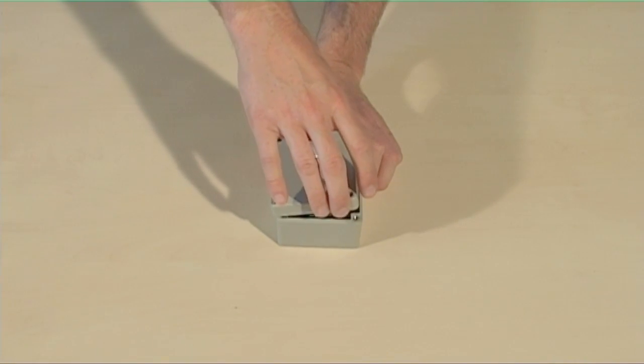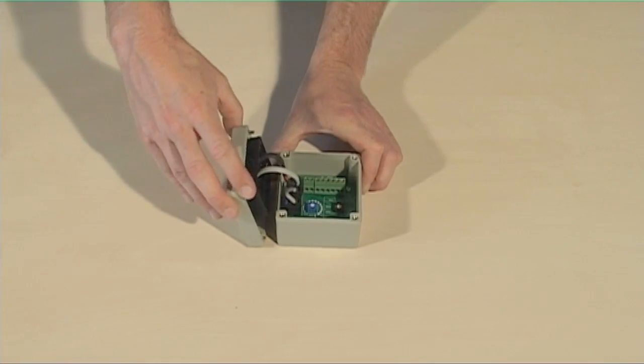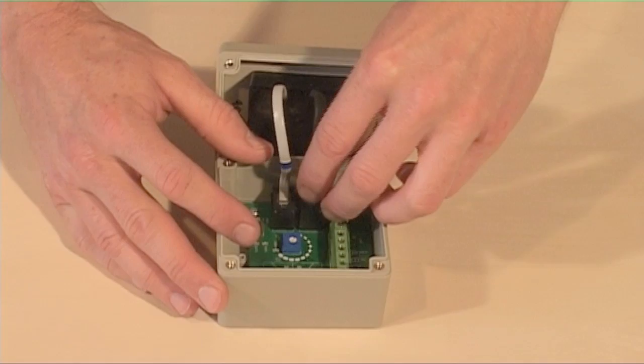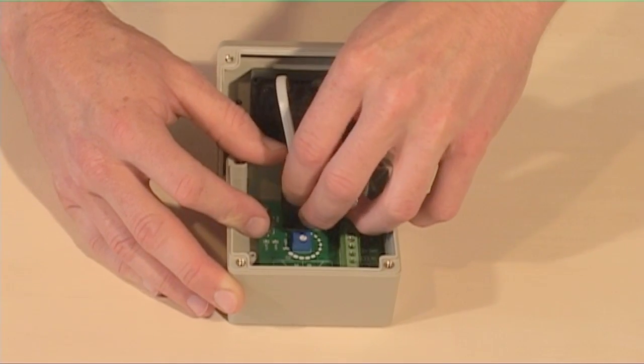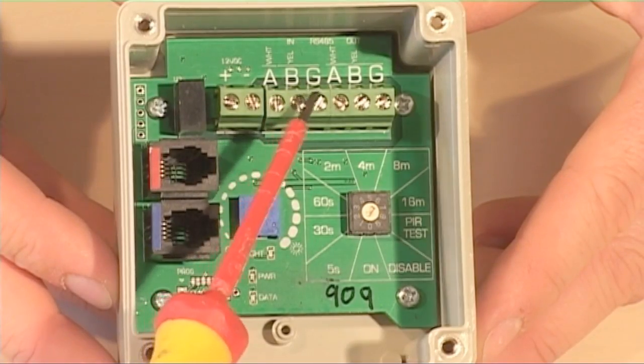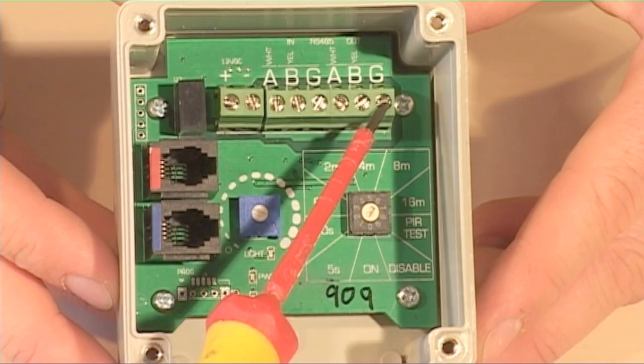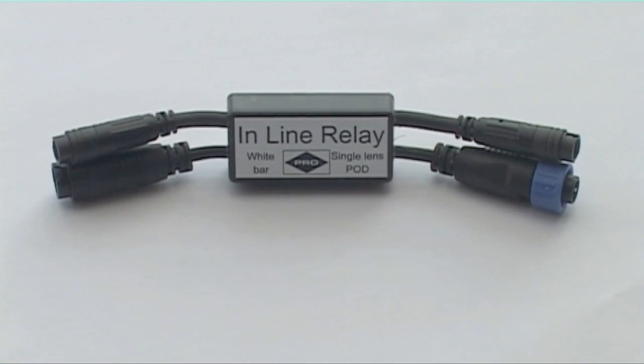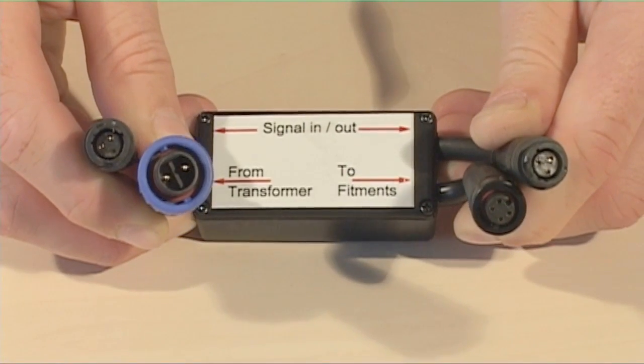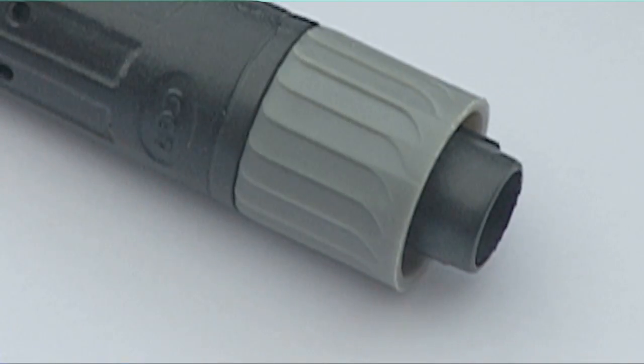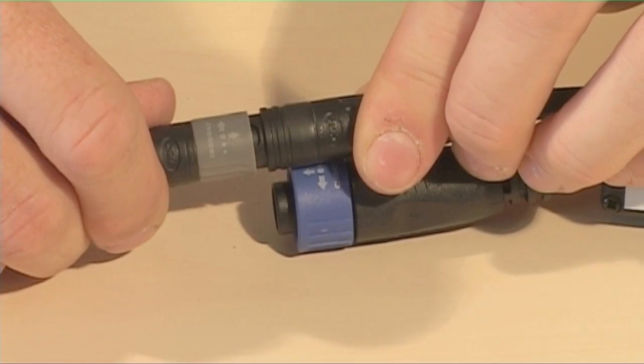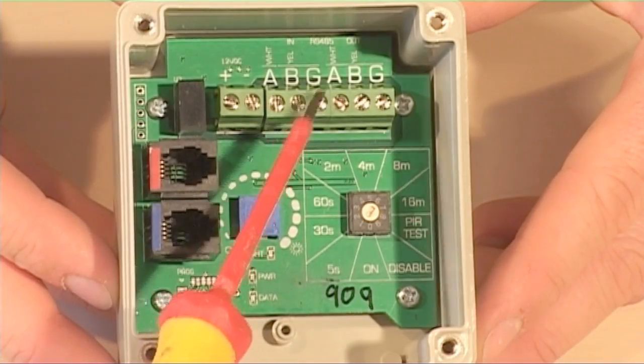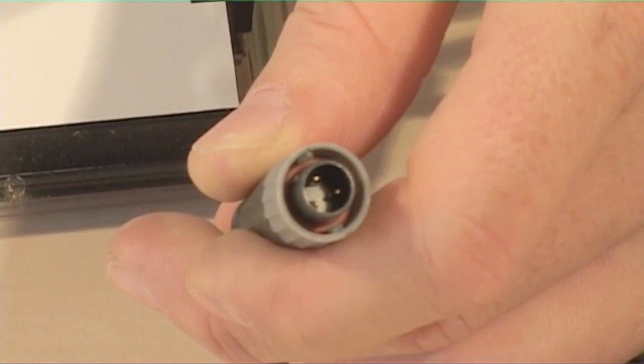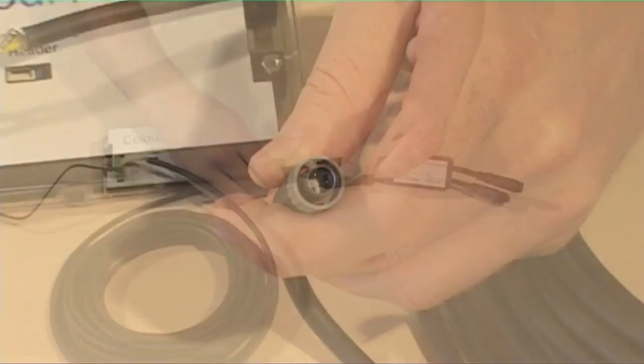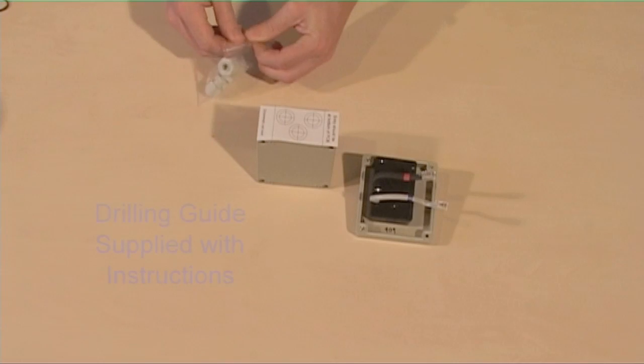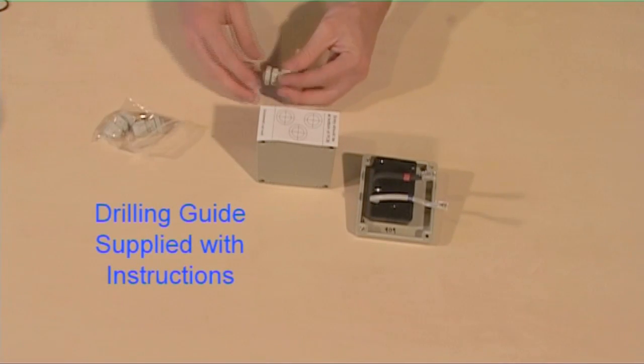Where day, night and motion detection is required, passive infrared detectors can be fitted. Take care when removing the front cover of the PIR, as there are connectors inside which may be attached. Inside the PIR, there are 2 places to make signal cable connections. The inline relay acts as a switch and is controlled by the PIR. A signal cable needs to be fitted between the PIR and the relay. The signal cables have 3 wires. If connection is being made to a PIR or to a color touch controller, then there are screw-down connectors on those devices. This cable has a 3-pin waterproof connector at one end. These connect like so. The cable passes through the enclosure wall using the glands supplied.